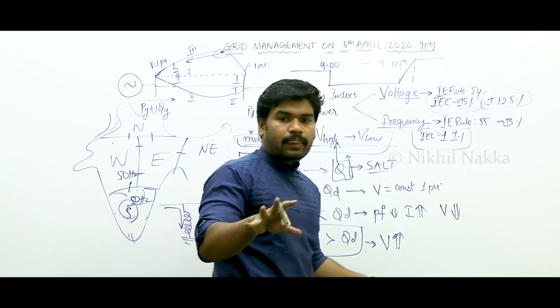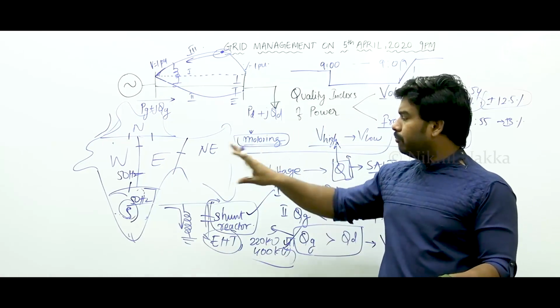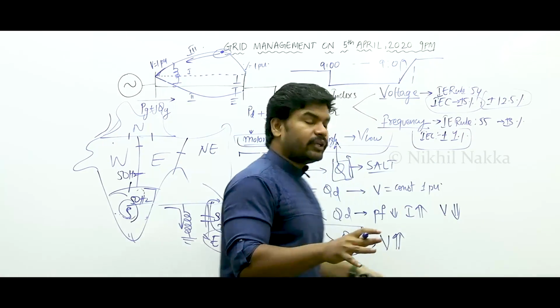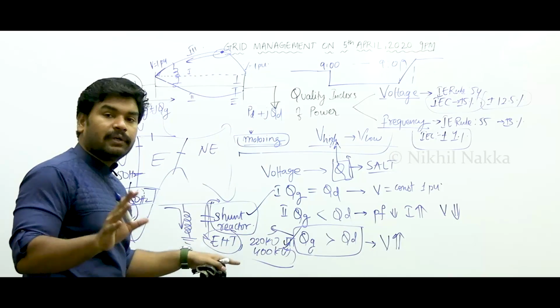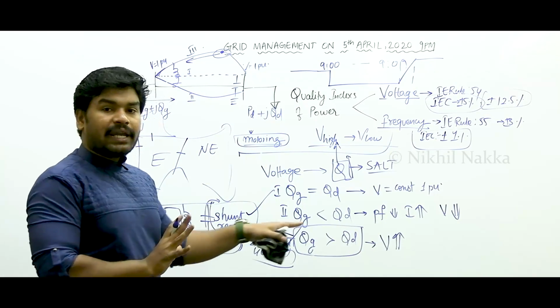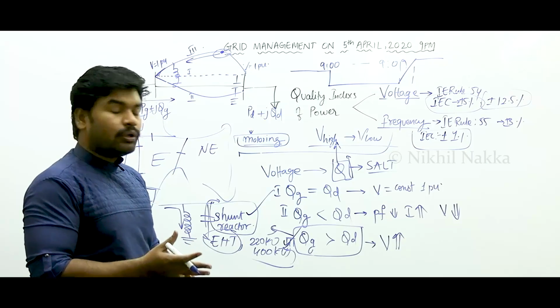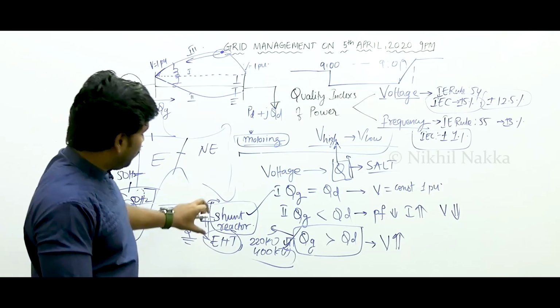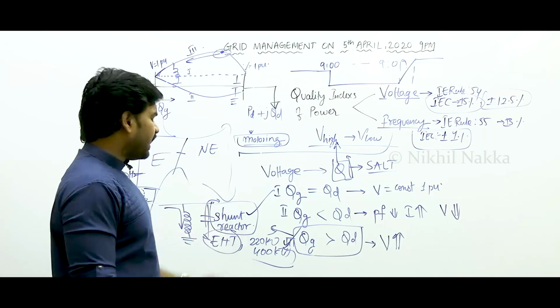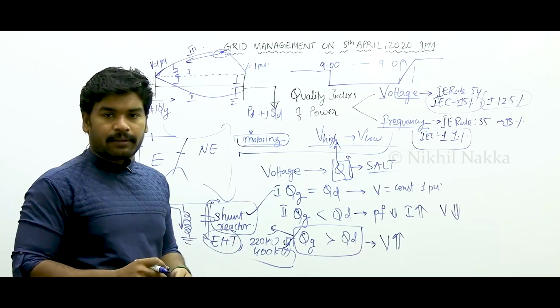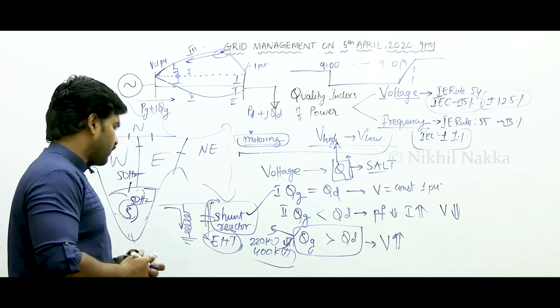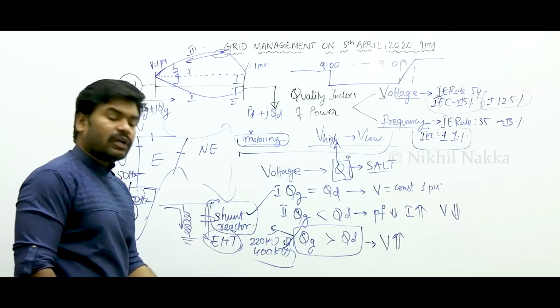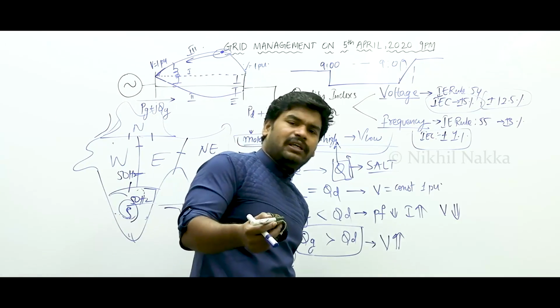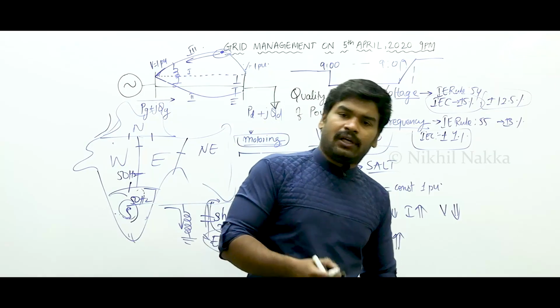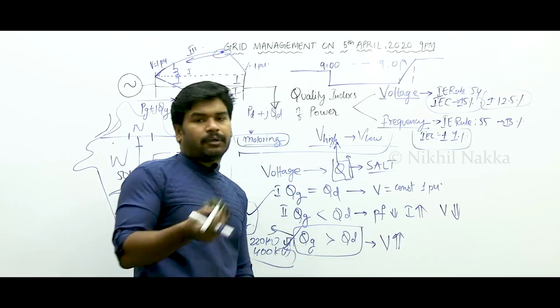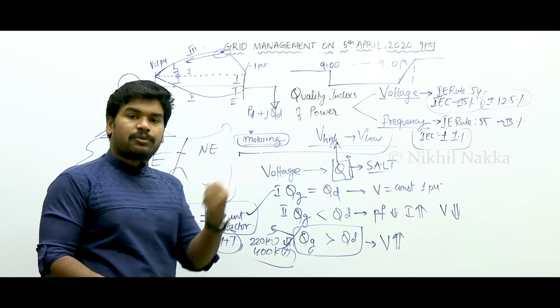So tomorrow also, all the big substations are going to gear up with this action of setting up the shunt reactors in order to manage what? The voltage rise. So to manage the voltage rise, what are we going to do? We will be needing what? Shunt reactors. At the same time, we will be needing somebody who will be consuming reactive power. So to consume reactive power, we are having shunt reactors. At the same time, we are also having FACTS devices like SVC and all these FACTS devices. So wherever there are FACTS devices, they will be kept into operation in a way to absorb the reactive power.